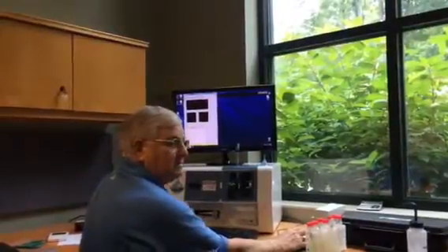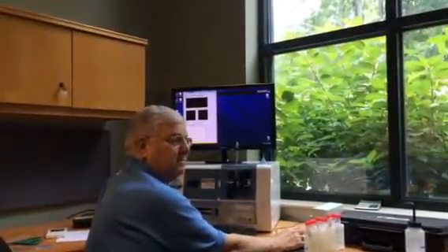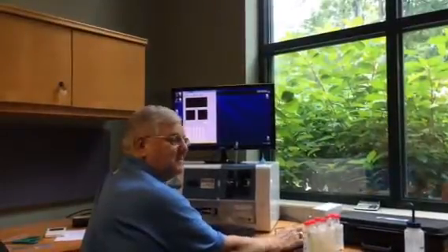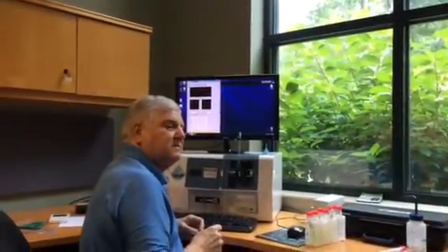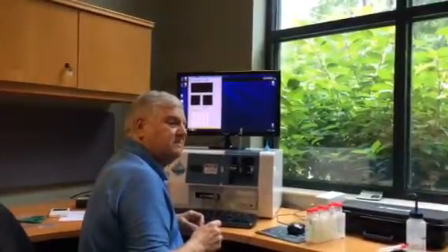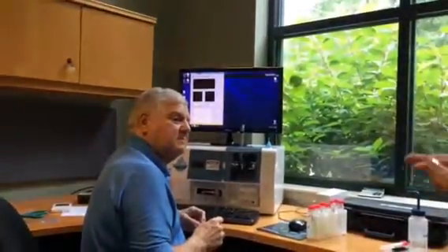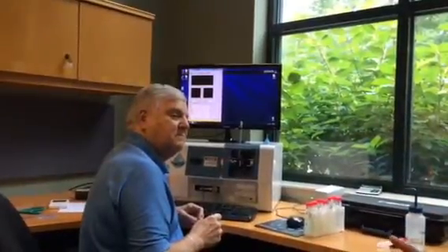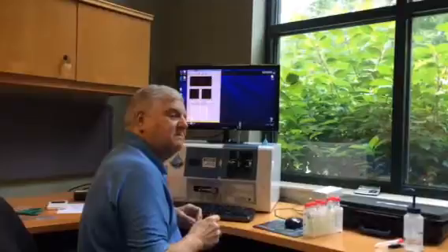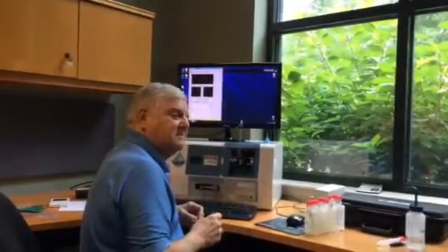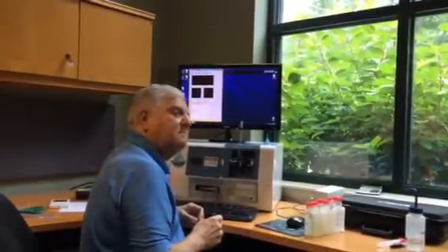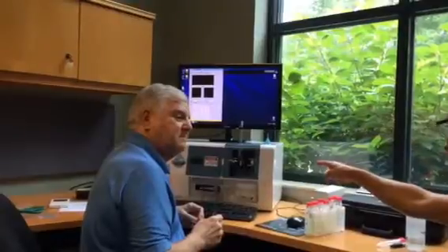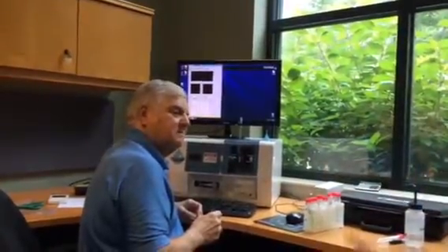Now you have a unique problem in that your sample settles so fast that, to have a high quality data run, I ideally want a pretty even distribution of particulate passing through the flow cell. So is it worth using that little trick I showed you yesterday, where you open auto image, build your notes, write out what the file name is going to be, and the notes are saved? Yes. Then hit Control-C, copy that file name, cancel auto image, go back to setup and focus, aspirate your sample so it's inside the top of the flow cell, and then begin.